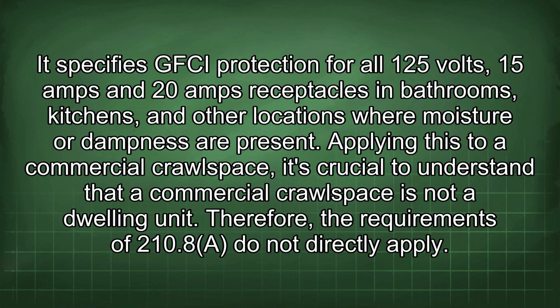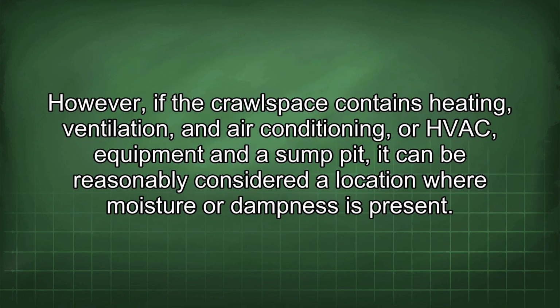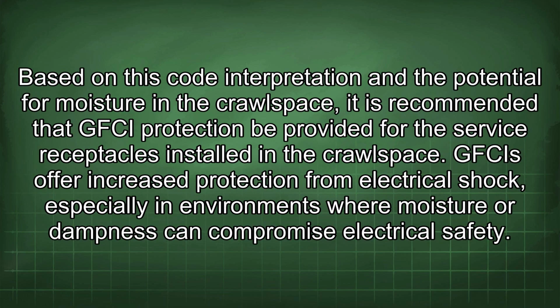Applying this to a commercial crawlspace, it's crucial to understand that a commercial crawlspace is not a dwelling unit. Therefore, the requirements of 210.8 do not directly apply. However, if the crawlspace contains heating, ventilation, and air conditioning, or HVAC, equipment and a sump pit, it can be reasonably considered a location where moisture or dampness is present. Based on this code interpretation and the potential for moisture in the crawlspace, it is recommended that GFCI protection be provided for the service receptacles installed in the crawlspace.